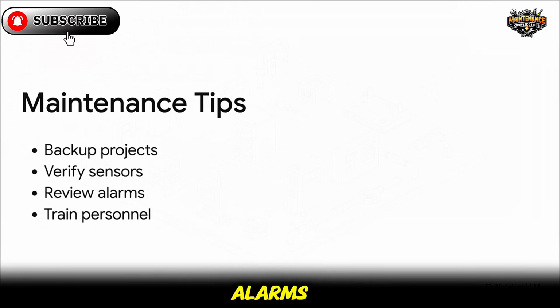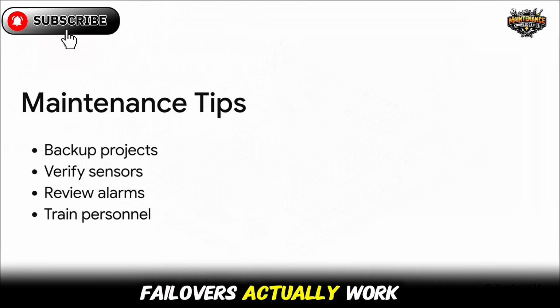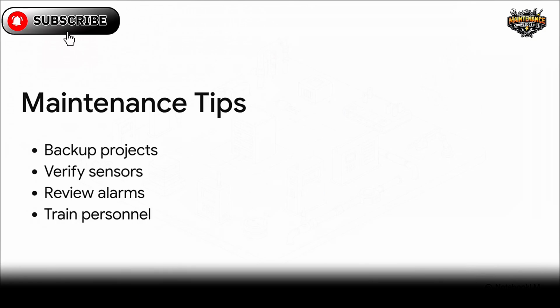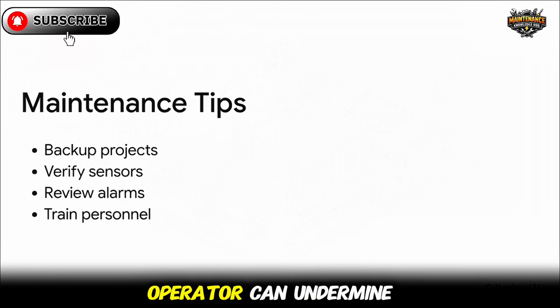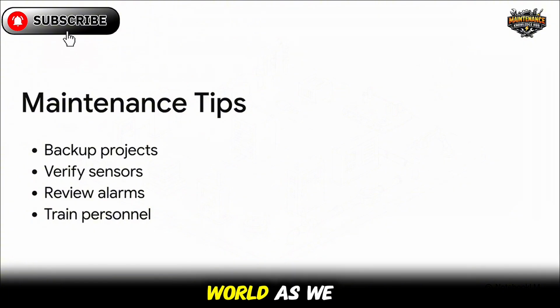4. Review your alarms. Eliminate the nuisance ones so operators only see what's actually critical. 5. Keep your software updated during planned windows. 6. Protect against cyber threats with strong passwords and firewalls. 7. Monitor server health. Watch your CPU and storage closely. 8. Test your redundancy systems. Make sure those failovers actually work before you're in an emergency. 9. Document every single change for traceability. And 10. Train your personnel. An untrained operator can undermine the best system in the entire world.